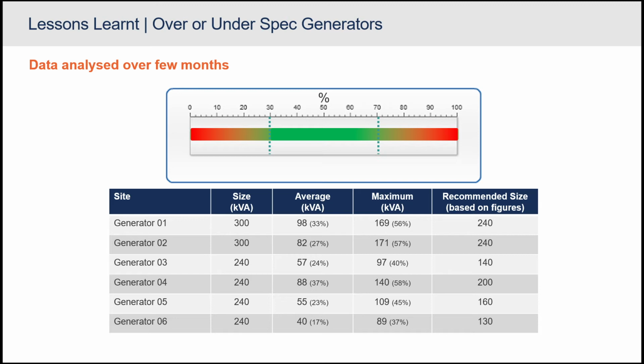You also don't want to plan for more than 70%, so that if something out of the ordinary happens, it can still cater for it. The sweet spot is anything between 30 and 70% of a generator's capacity. Running it below that is really bad for the generator and dramatically reduces your asset life.